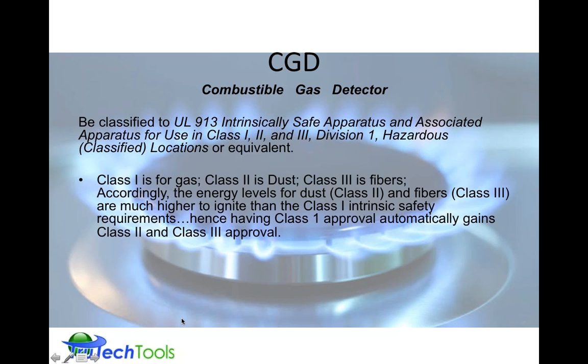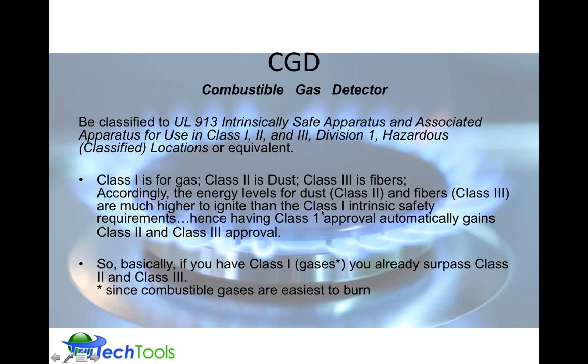What Class 1 means: Class 1 is for gases, basically, hazardous gases. Class 2 is for dust, and Class 3 is for fibers. The energy levels required for dust to combust and be explosive, and fibers, are much higher than Class 1 intrinsic safety requirements. And this is usually the case that having a Class 1 approval automatically gains Class 2 and 3 approval, because the intrinsic safety requirement is the most stringent for Class 1. So basically, if you have Class 1, which are gases, you already surpass the Class 2 and 3 requirements, since combustible gases are easier to burn than dust and fiber concentrations.